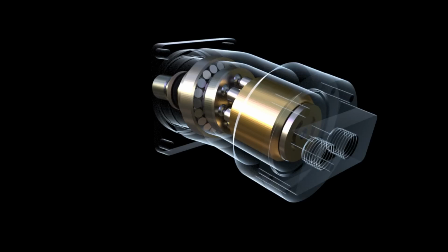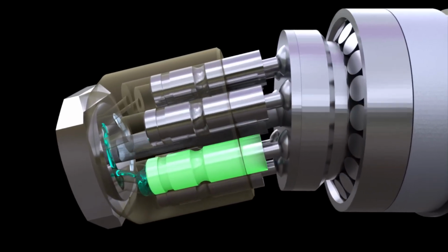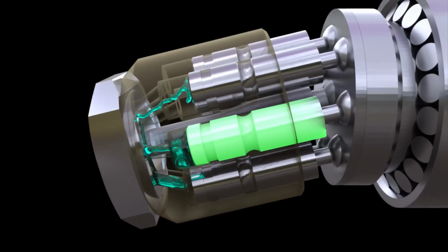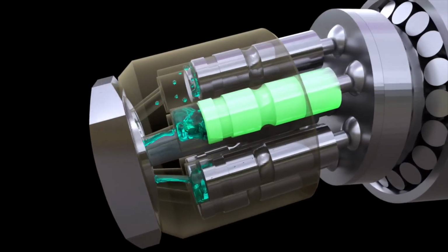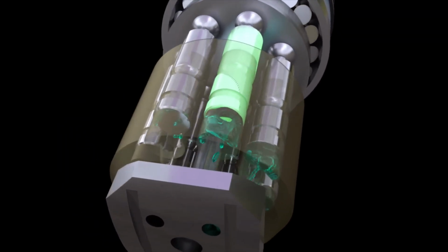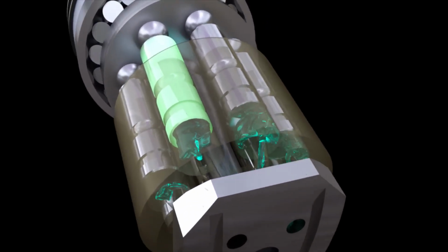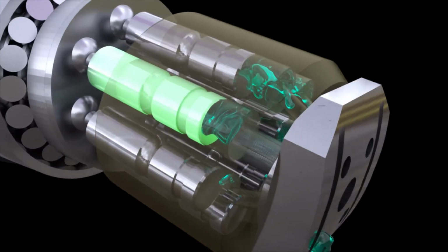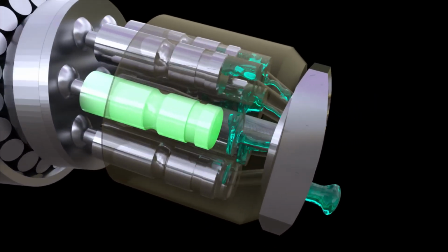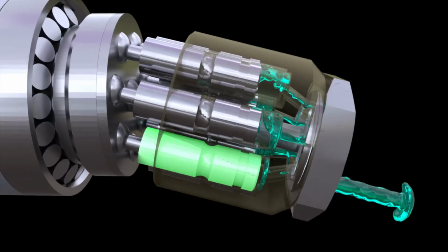The fluid from the tank is supplied to the inlet channel of the pump, from where it is sucked by the pistons. Consider the operating principle of one of the pistons. When moving through the suction area, the piston moves and increases the volume of the working chamber. Due to the increase in the volume of the chamber, the pressure in it drops and the fluid fills the chamber under atmospheric pressure. Having reached the extreme position, the piston begins to move in the opposite direction, thus reducing the volume of the working chamber, and the fluid is displaced into the pressure channel.